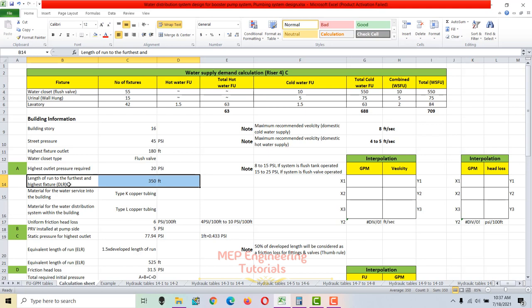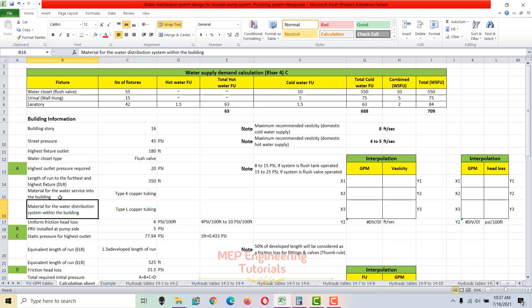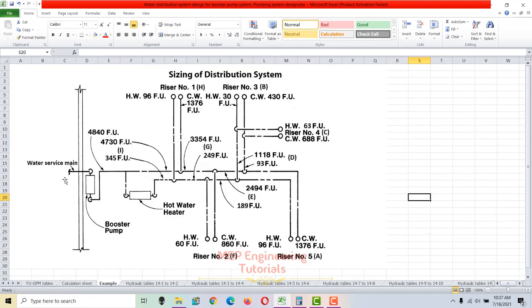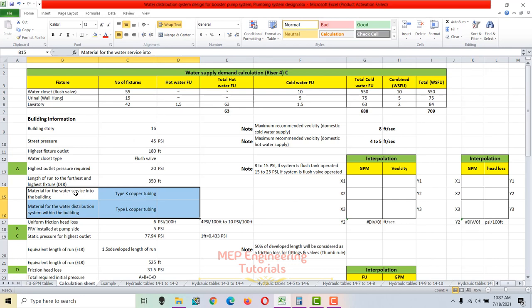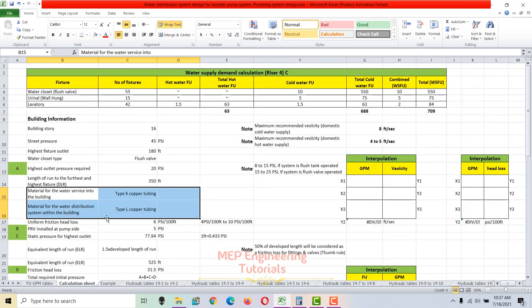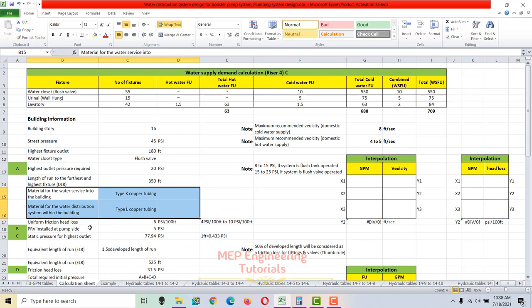Material selection is very important because the hydraulic tables are prepared based on material. Tables 14-1 through 14-12 are used here for sizing. The material for the water service into the building is Type K copper tubing, while the material for the water distribution system within the building is Type L copper tubing.